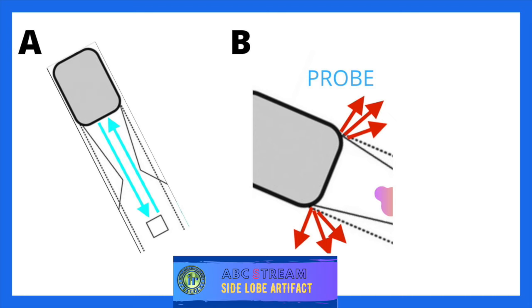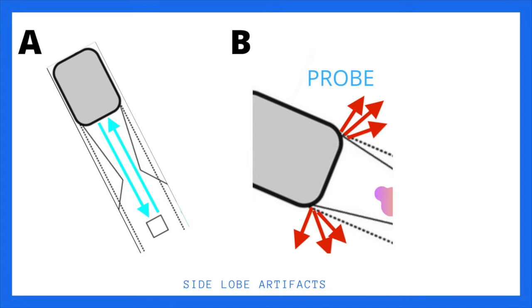The S in ABC STREAM is side lobe artifacts. Normal structures reflect back sound, but there are also low amplitude ultrasound energy beams that project radially from the main beam axis. These radially projecting beams can hit structures on either side of the main imaging field, and if those structures are highly reflective they return a signal back to the transducer. This is known as a side lobe artifact.